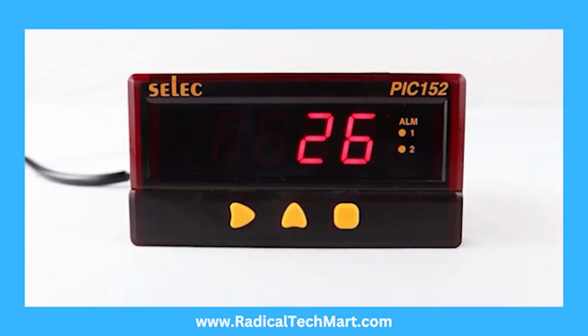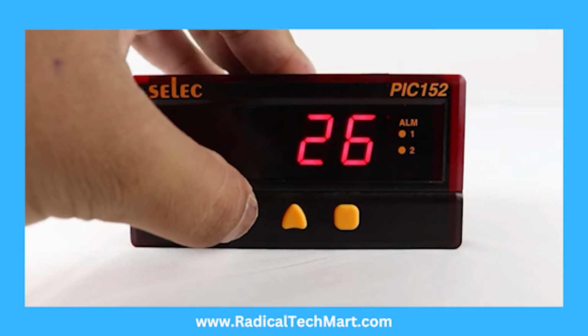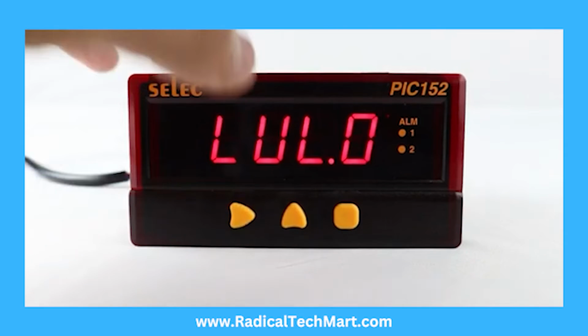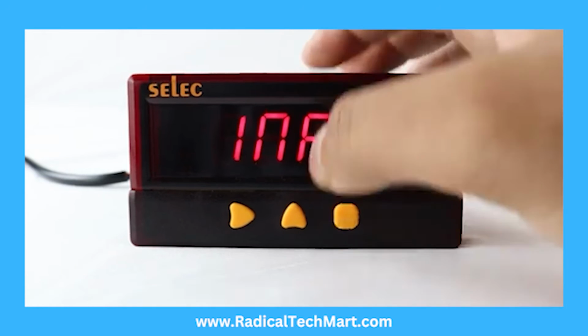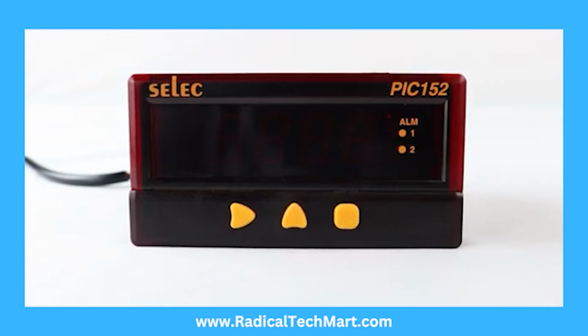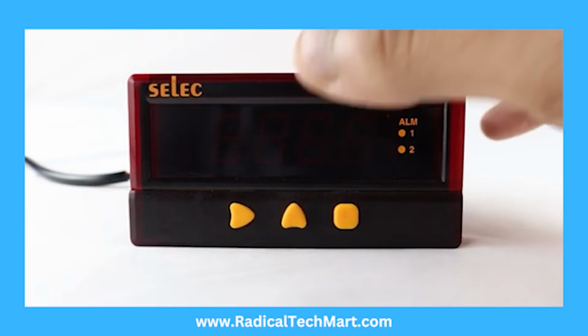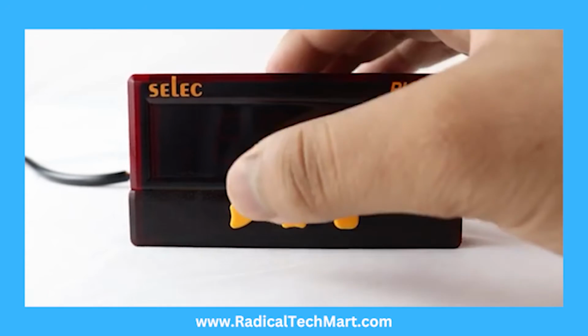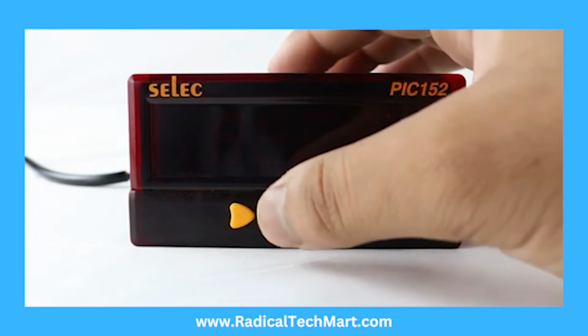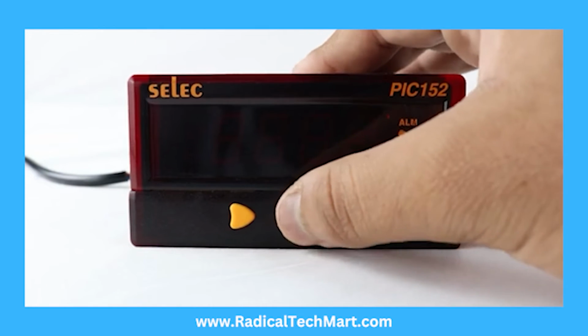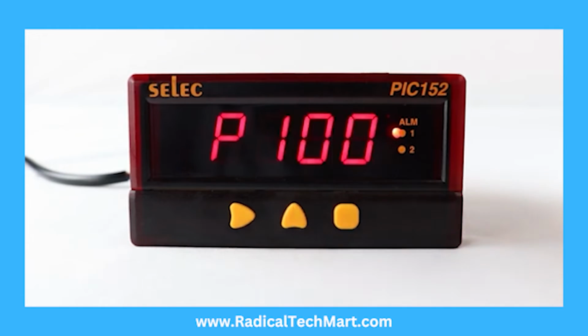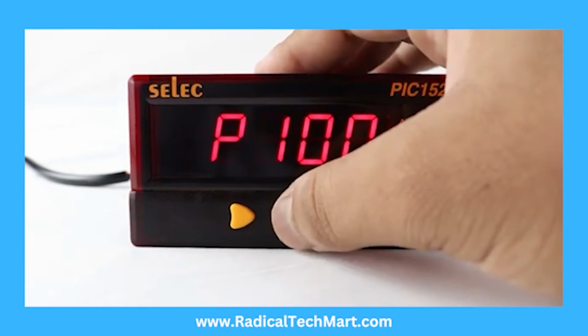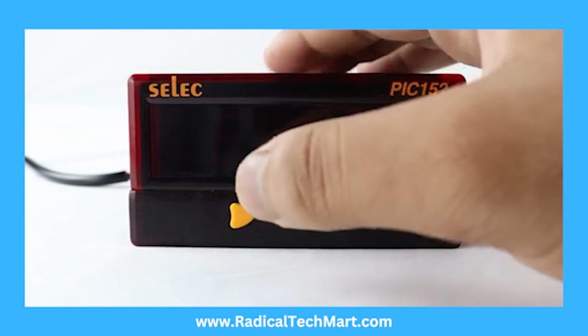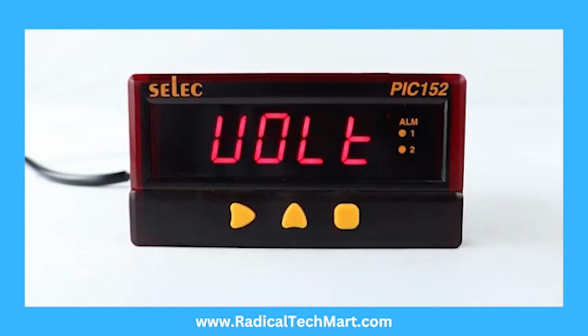Programming. Long press the right arrow key for 3 seconds to enter configuration level 0. Press the square key to select input sensor type, wherein you can toggle between various input sensor types, which consist of J-type, K-type, T-type, R-type, S-type thermocouple, RTD PT100, millivolt, voltage, and current, by pressing the up arrow key.